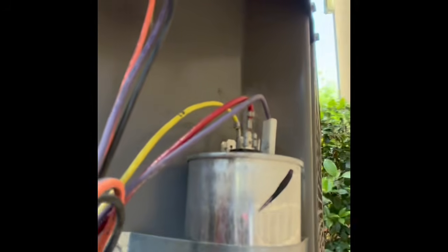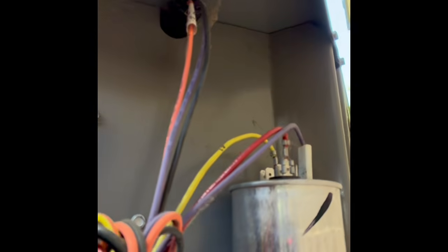There you can see these top 2 lugs is where the high voltage comes out, and you got a wire that goes to the capacitor, into the fan motor, and to the compressor. Over there is our capacitor. We'll test that in just a moment.